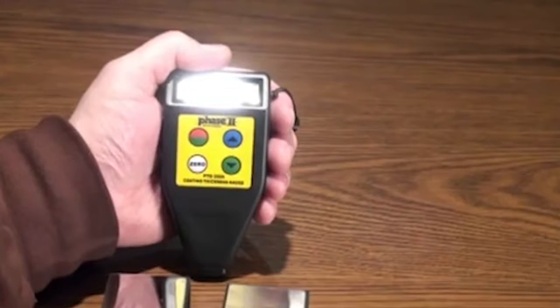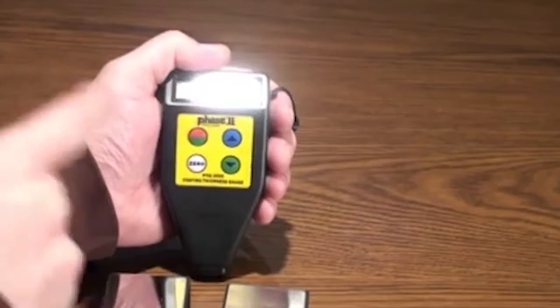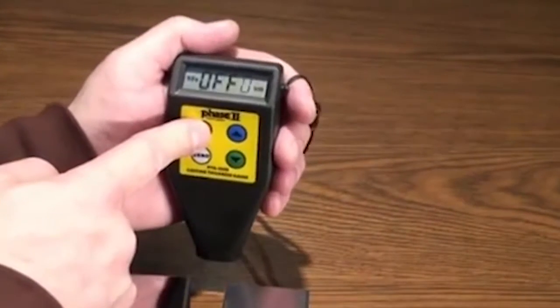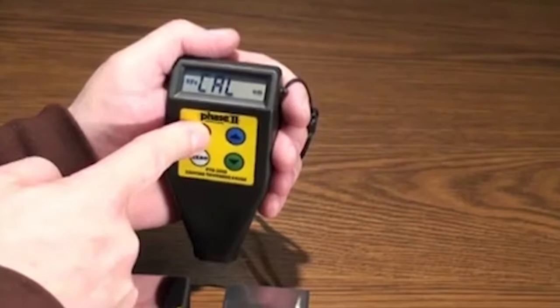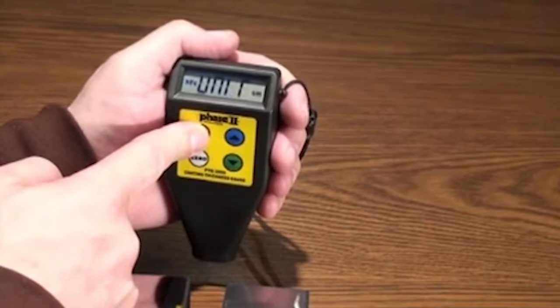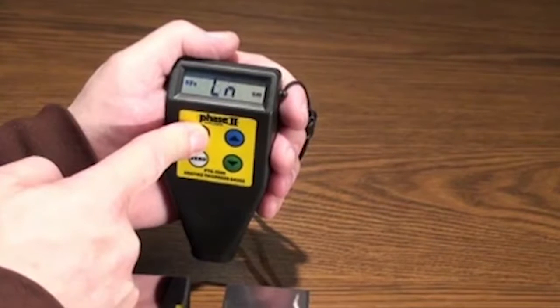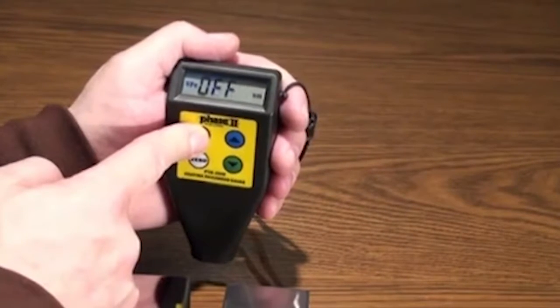The power key also acts as a menu key. If you hold down the menu key for a few seconds, you will see the screen change first to OFF, then CAL, then UNIT, then SC, then LN, and finally back to OFF.